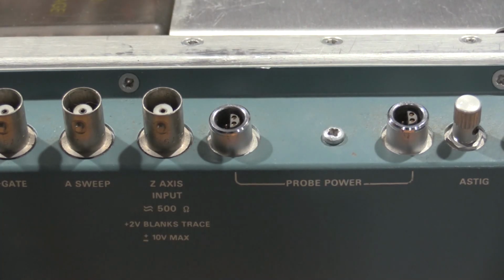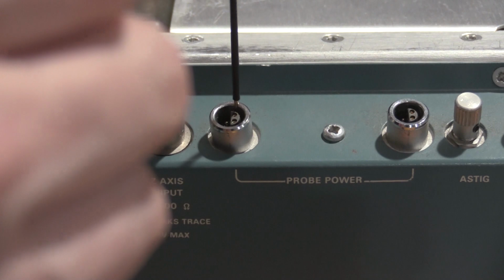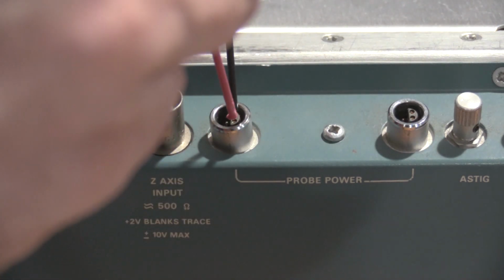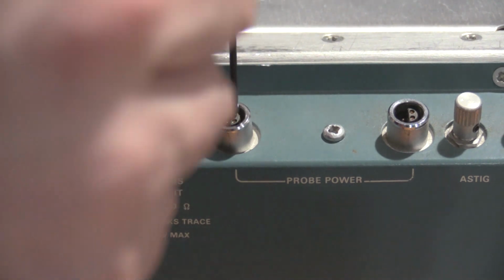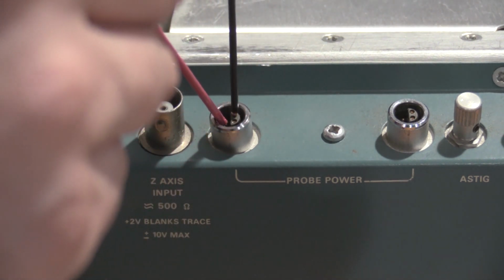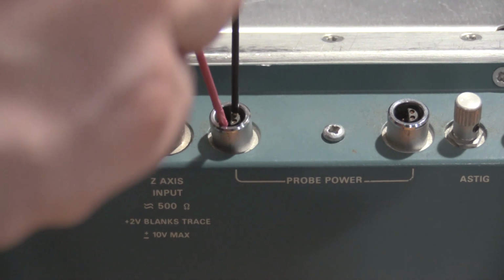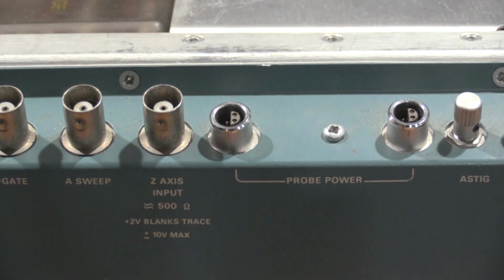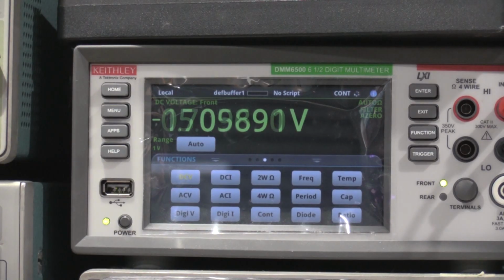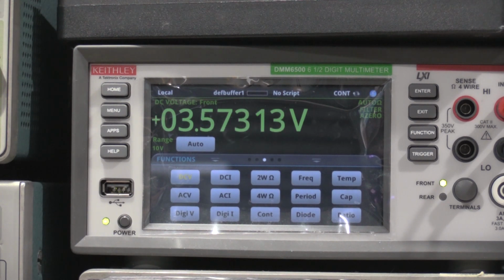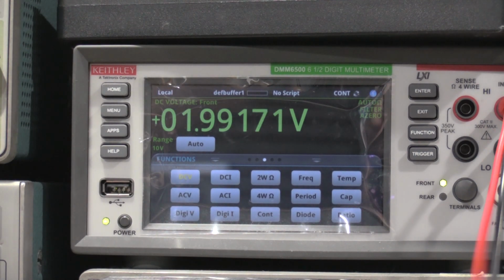All right, next we're checking probe power. So I'm going to do this on the probe, and then I will show you guys the meter next. So +5, -15, +15 looks good. While I check the other probe power. +5, minus 15, plus 15. Those are good.